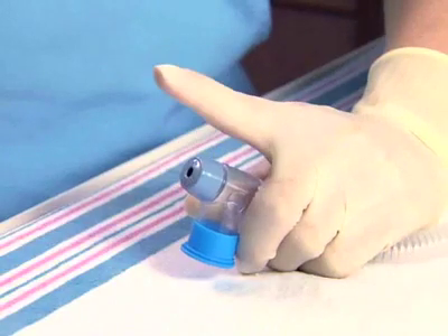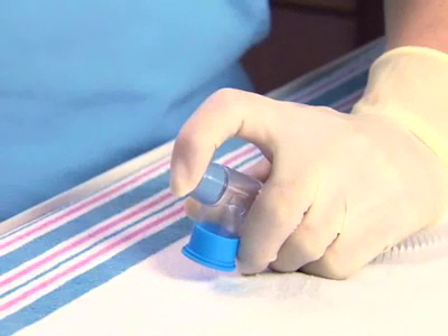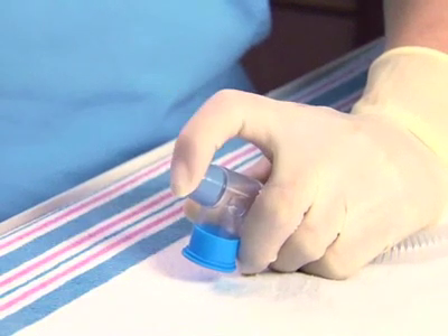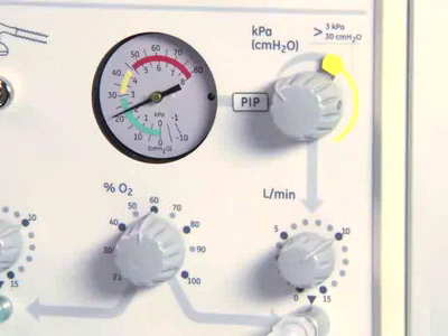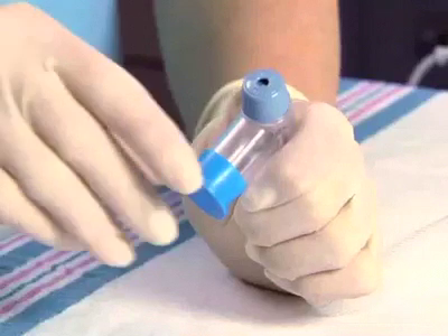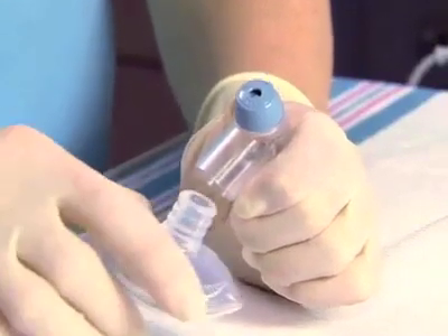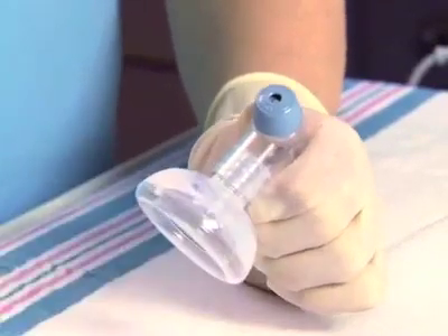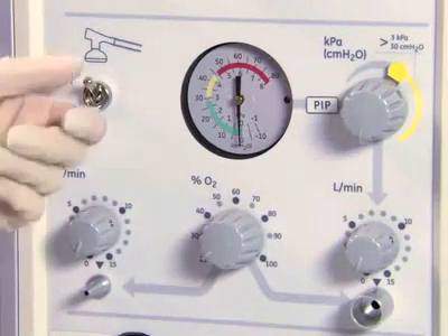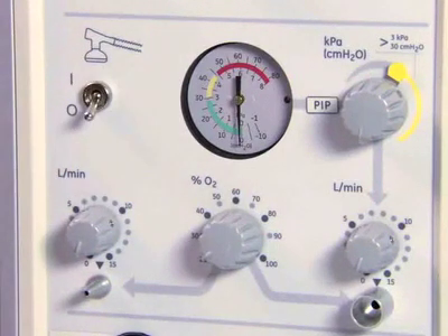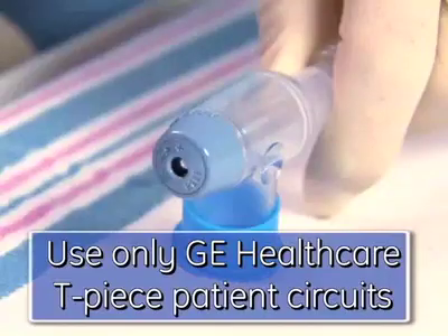Perform a few practice breaths by using your thumb or index finger to occlude the PEEP control knob. Watch as the manometer gauge shows your PIP and PEEP. Remove the blue end cap and attach a neonatal face mask. Turn the medical gas switch off until ready to initiate resuscitation or airway support measures. Use only GE Healthcare T-piece patient circuits.